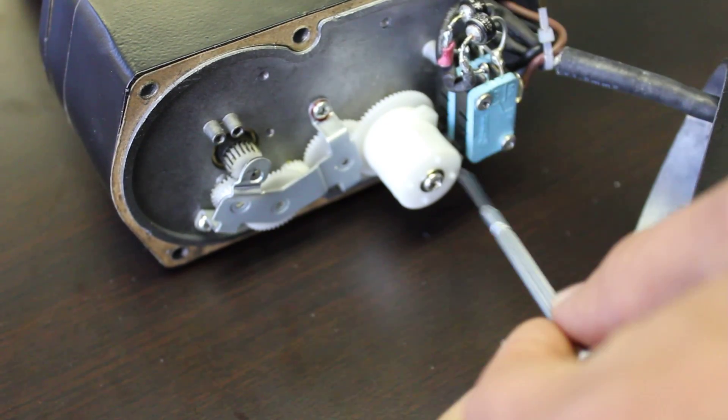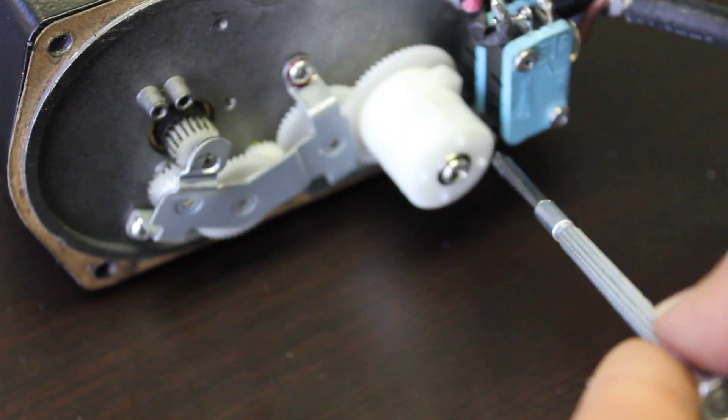And you'll notice right over here, this is where the limit switches are located. Basically how it works is there's a little arm on the lower and upper limit of the limit switch that turns as you extend or retract. That arm ends up touching the limit switch, which cuts the power.